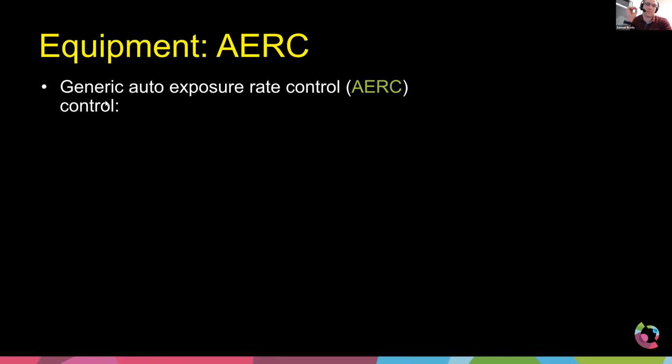So what we need to do to get good image quality and good noise control starts before the first patient even walks into the room. The medical physicist needs to work with the system. They need to measure the amount of radiation dose at the detector, that EERD, the entrance exposure rate to the detector, and make sure it's comparable as they go from 30, 15, 7.5.